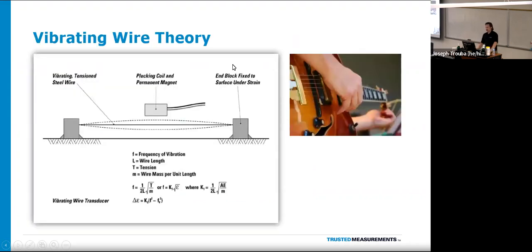So to get into vibrating wire theory, how these instruments work, the internals of them, think of it like a musical instrument. So I put this guitar player up here on this slide. You can think of it like a guitar wire or a piano wire, strung between two fixed points. In this diagram on the left here, we have a vibrating wire, typically a steel wire, in tension between two fixed points. On top of that, you have a plucking coil and permanent magnet assembly.